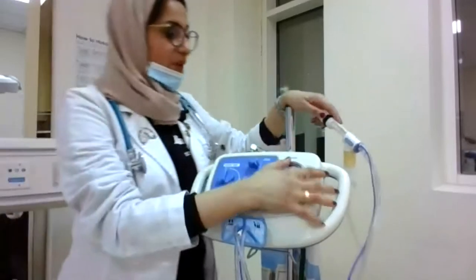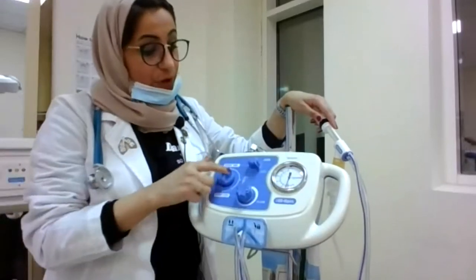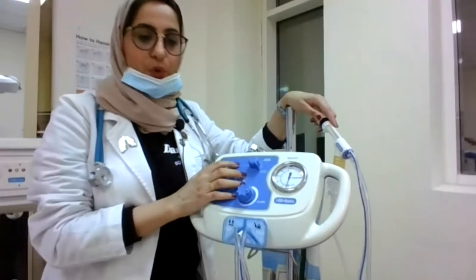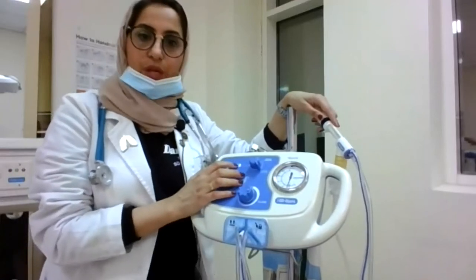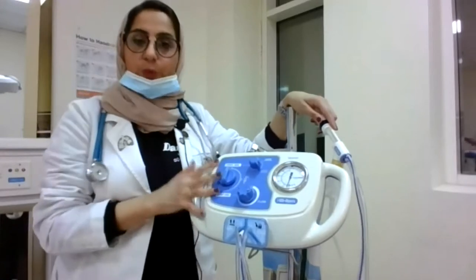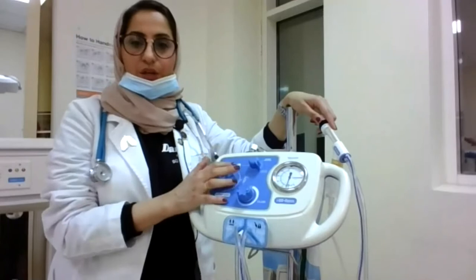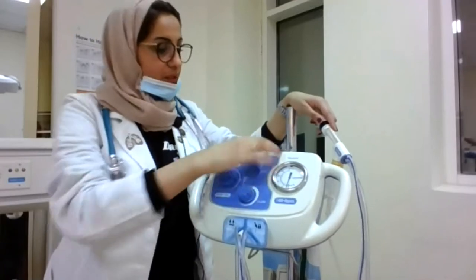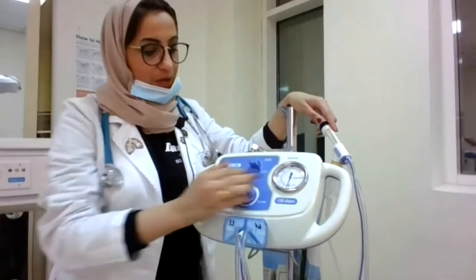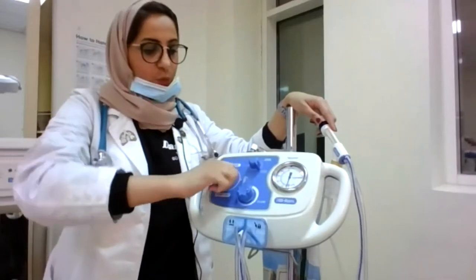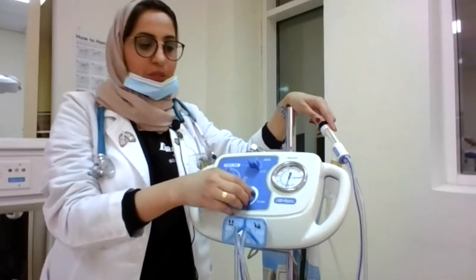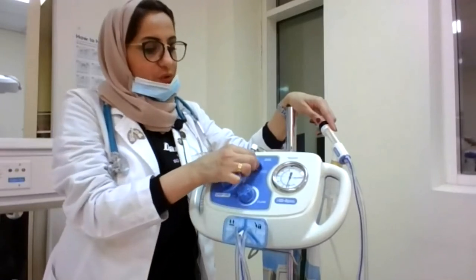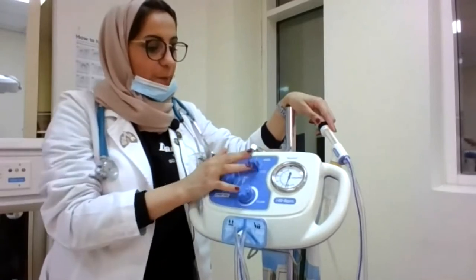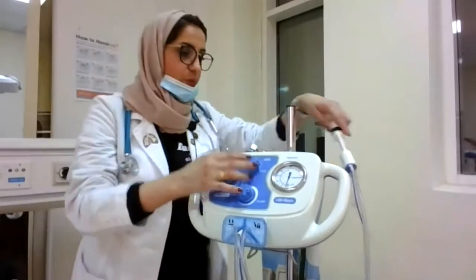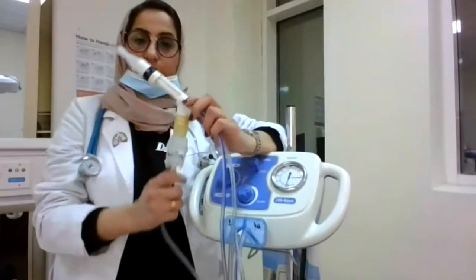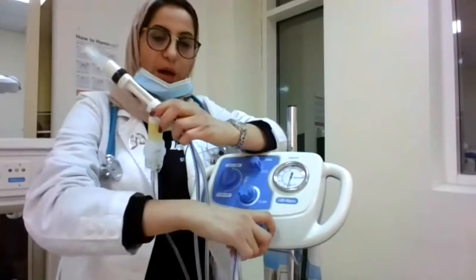Okay, this is the device. This is the on and off button. The third mode that I haven't discussed is the aerosol therapy only mode. During this mode, the other 2 modes will be off. So we will be only providing aerosol therapy through that mode. This is the on and off button. This is a manometer. This is the knob where we change the modes, and this is the knob to increase and manipulate the flow, and this is to change the frequency of the continuous high frequency oscillations mode. This is the mouthpiece, the handle, nebulizer, tubing, and biofilter.